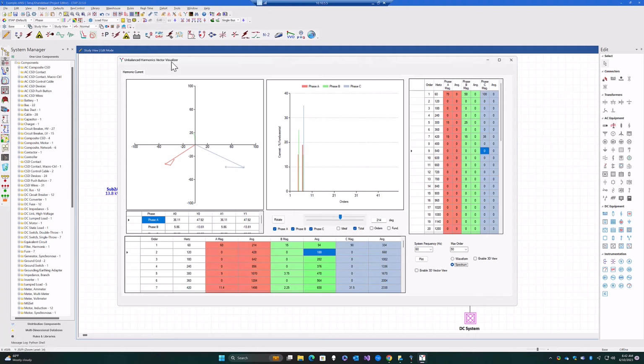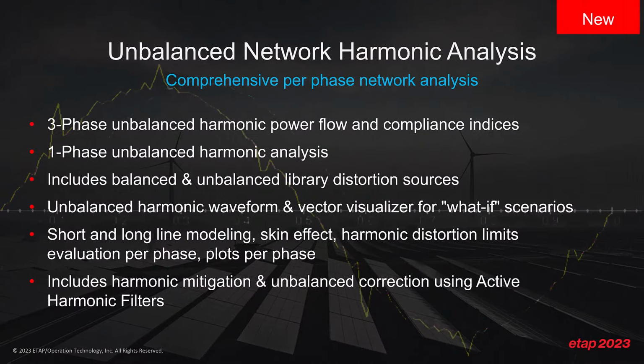The unbalanced harmonic vector visualizer, which is new in ETAP 2023, is just a quick means for you to investigate the impact of unbalance, harmonics, and a combination of unbalanced harmonics in a simple to use visualizer, also for educational purposes. But the main addition in ETAP 2023 is the unbalanced network harmonic simulation that includes a full three-phase unbalanced harmonic power flow along with the frequency scan. So let's take a look at the unbalanced network harmonic analysis in action on our single line diagram.